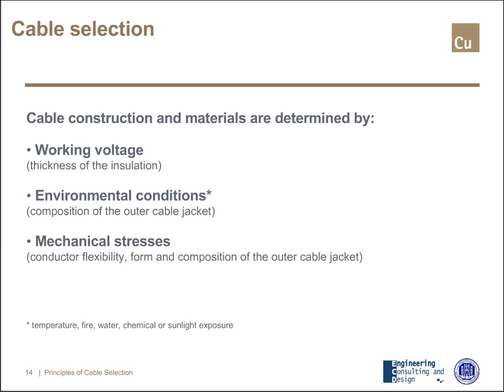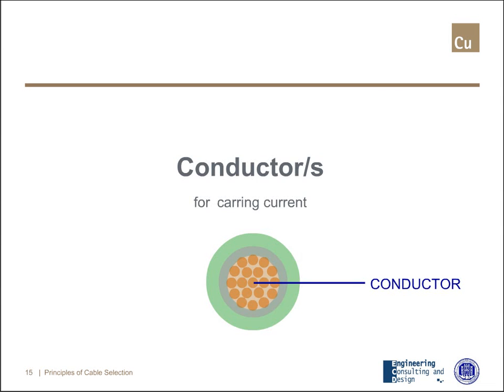The last class of stresses are mechanical stresses. These stresses affect conductor flexibility — or more generally, cable flexibility, form, and composition of the outer part of the cable. Mechanical stresses, as well as environmental stresses, are to be referred to the working condition of the cable as well as to the installation phase. This is very important for mechanical stresses, because during installation in certain cases the cable can be stressed mechanically much more than during its working life, and this must be taken into account when selecting the cable.